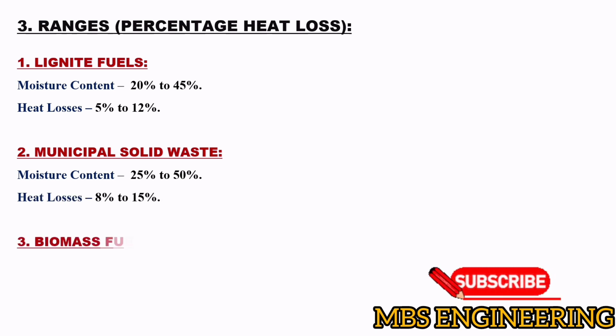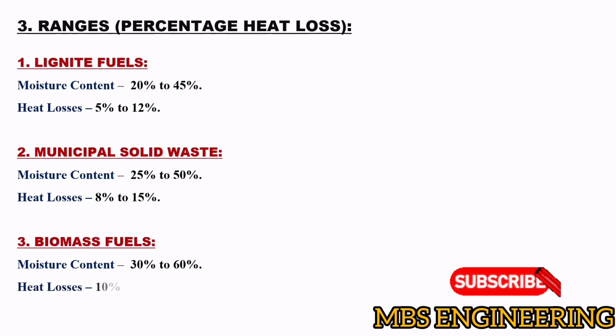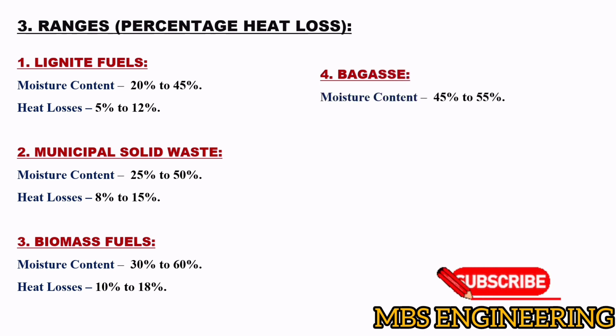Next, in biomass fuels, its percentage of the moisture content ranges from 30% to 60%. Its percentage of the heat losses ranges from 10% to 18%. Next, in bagasse, its percentage of the moisture content ranges from 45% to 55%. Its percentage of the heat losses ranges from 12% to 20%.